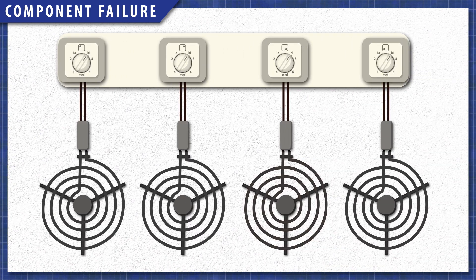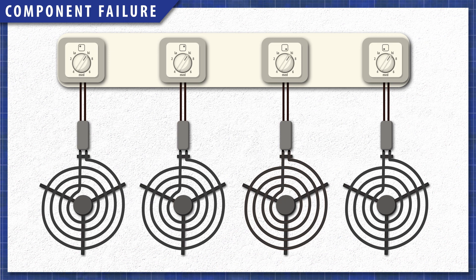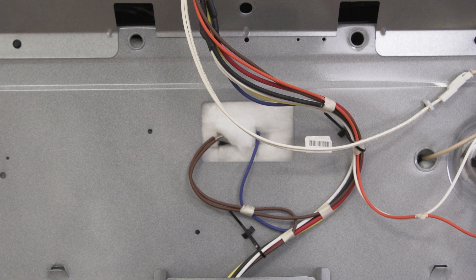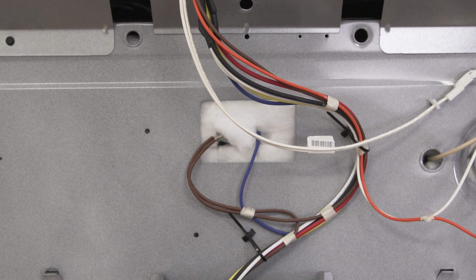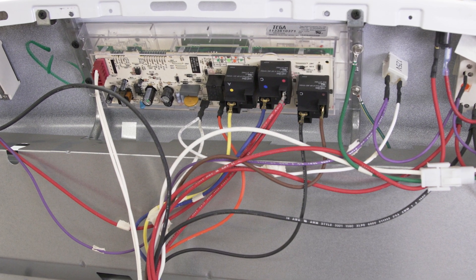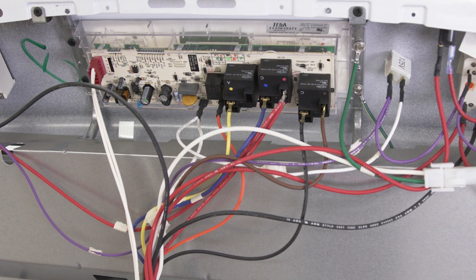Now, if all the heating elements are not working, then it's likely a blown fuse, or an issue with the power source. In any scenario, it's best to visually inspect all wires and components, looking for burn or scorch marks around the terminals. This can also help you narrow down the failure.